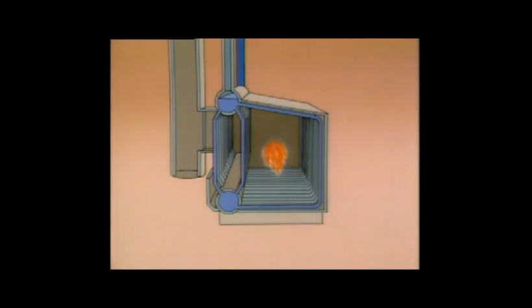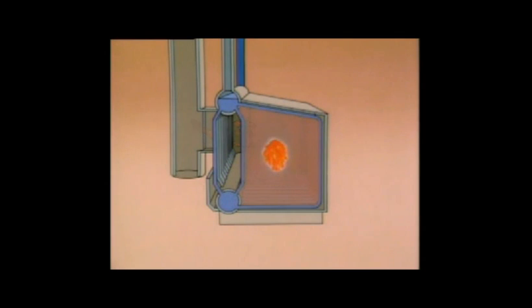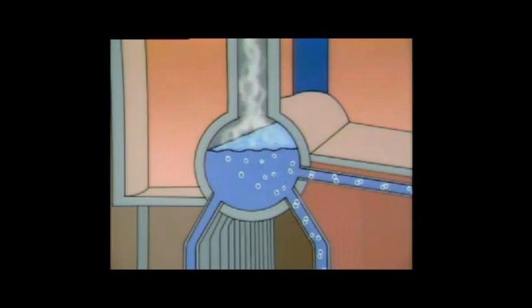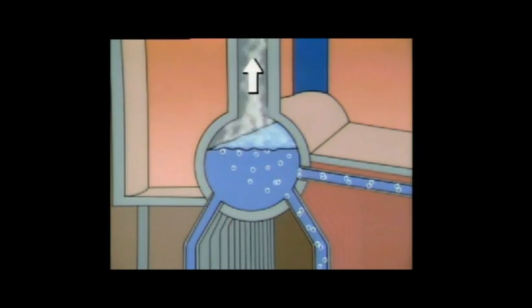As fuel is burned in the combustion area, heat is transferred to the adjacent water tubes, and the combustion gases then flow out of the boiler. Water circulates from the upper drum through the water tubes and into the lower drum, often referred to as the mud drum. From the lower drum, water is distributed to the water tubes surrounding the combustion area. As the water in the tubes is heated, a steam-water mixture is produced. The steam-water mixture enters the upper drum, where the steam is separated from the water and routed through the steam outlet and into the plant.